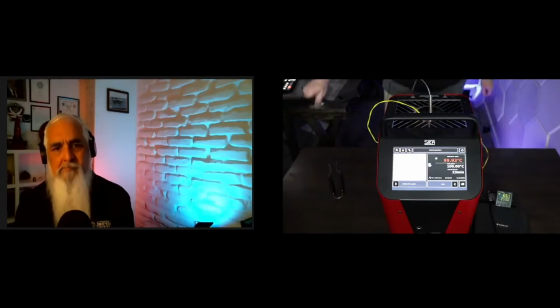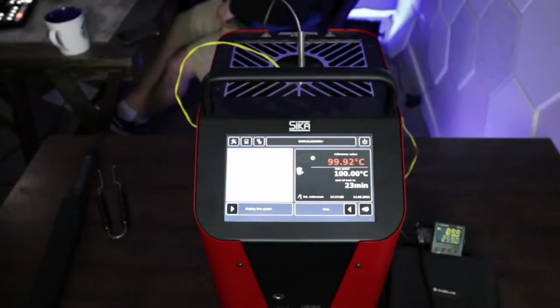Just for reference, I'm going to put in one that's just a very simple thermocouple where I've just connected these. This is what you're going to see all the time out in the field, people measuring. This is a thermocouple to them, and it's not. Everybody should know that. But here, I'm going to hook that one in real quick. So let's look at the difference in response time for that one. Does that make sense? Yeah. There's probably a good portion of people in their kitchens that have thermocouples and don't even know what it is. Oh, yeah, for sure.